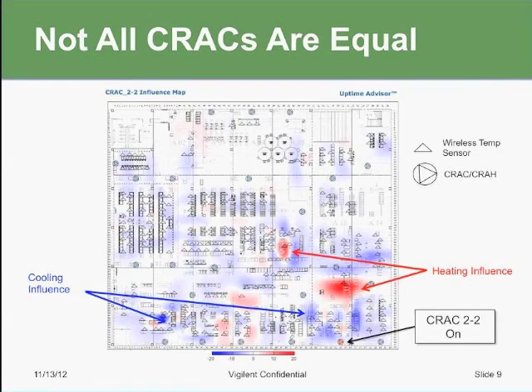Now, the last example I discussed was a simple one-CRAC model. But of course, in the practical world, a data center room has many CRAC units: 20, 30, 40, or even up to 100 cooling units in the same space. And this image that you're looking at here is an influence map from a Vigilent system. And it's showing the relationship between cooling units and how that affects temperatures in the data center. And so this unit, CRAC 2-2 in the lower right-hand side, when that unit is operating, it is influencing the temperatures as shown in the color gradient. So all the areas in blue is where it actually gets colder, but the areas in red is where it actually gets hotter. And this is surprising to people.